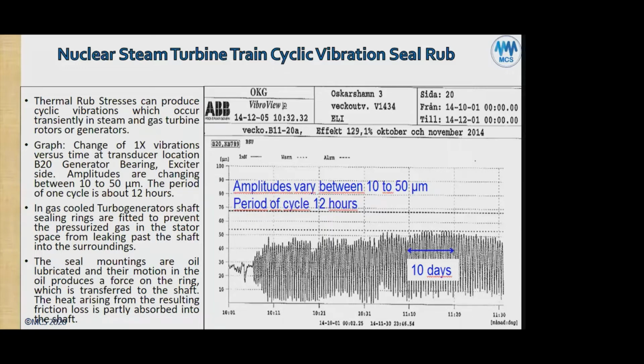The other possibility is that if their lube oil temperatures are varying from day to night significantly due to the cooling water, for example, then it could be that the change in oil temperature, meaning viscosity, is also feeding this variation in amplitude. Okay, and that would be in the bearings themselves, the generator bearings.